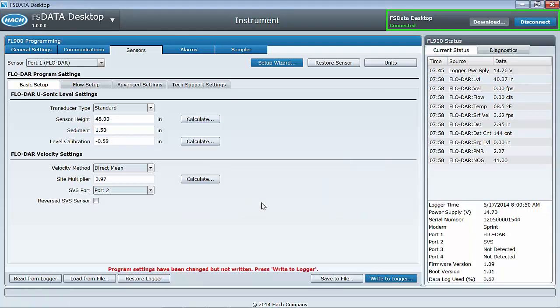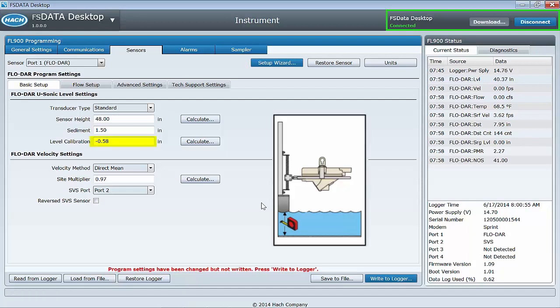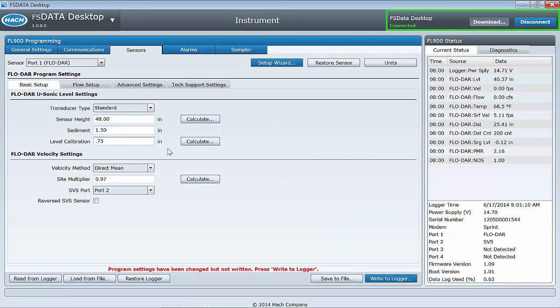Method 2: Enter a positive or negative offset in the field here to make the value received in current status or a diagnostic reading match your physically measured level, and then write to logger.